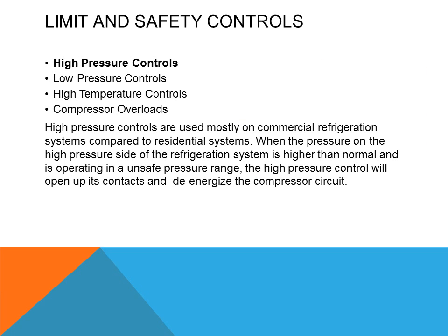High pressure controls are used mostly on commercial refrigeration systems compared to residential refrigeration systems. When the pressure on the high pressure side of the system is higher than normal and is operating in an unsafe pressure range, the pressure switch will open its contacts and de-energize the compressor circuit.